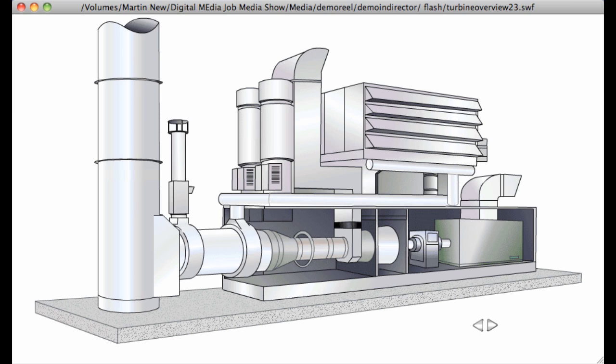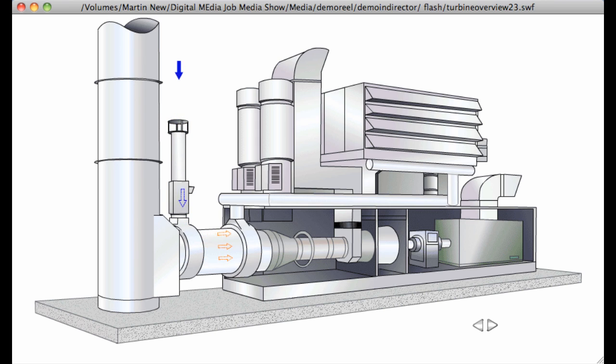That's a quick look over the main turbine and generator sections of this unit. We'll finish now with a look at a few of the other externally visible features of the package. This is the inlet air duct for the anti-icing system. A fan draws air into the top of the duct. It passes through a set of tubes in the anti-icing heat exchanger where it's heated by the exhaust gases from the turbine.